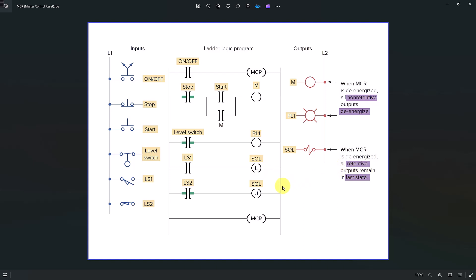Another example of retentive output is a counter, and the other one is the retentive on-delay timer. The retentive on-delay timer is able to hold the accumulated value in the last state. For example, if the accumulated value is 200 and it de-energizes, the value will remain 200 — unlike the normal on-delay or off-delay timer where the accumulated value resets to zero. So there are three retentive outputs: the latched/unlatched virtual output coil, the counter, and the retentive on-delay timer.